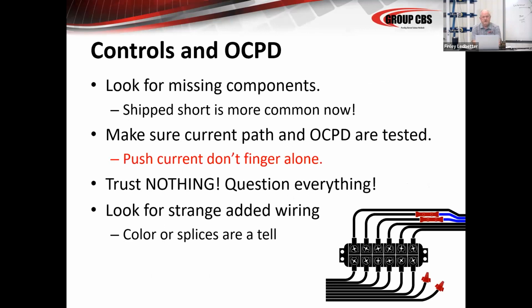Controls and overcurrent protective devices. Look for missing components with new switchgear. Quite often you will find a component that's missing. There'll be a tag on it and the tag says being shipped later. Or it'll be in a cardboard box up in the instrument compartment because they didn't get it installed, but they shipped it with the gear. And you see that more often than you might think. So watch for things that are shipped short.